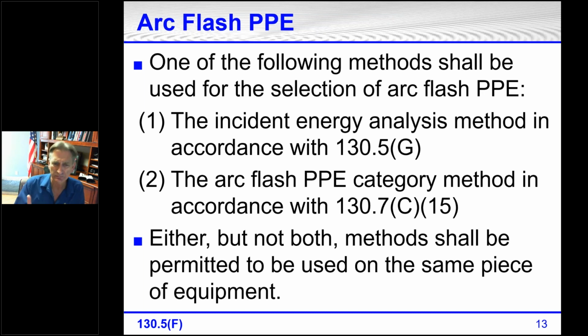70E says that all the equipment that's liable to be adjusted, serviced, or maintained while it's energized has to be labeled with the information. And so this is one option, where you have arc flash labels on equipment that give us a certain amount of information. It gives us the arc flash boundary. It may give us the category. It may give us the incident energy at 18 inches. And we have information that we get off of that.